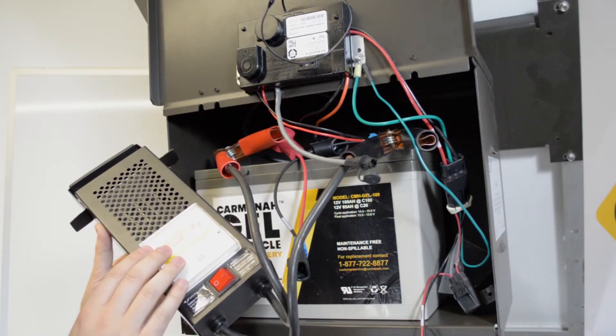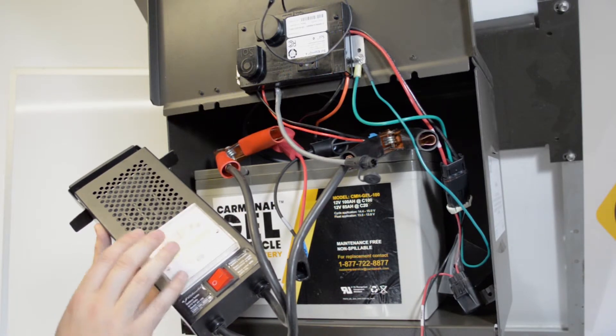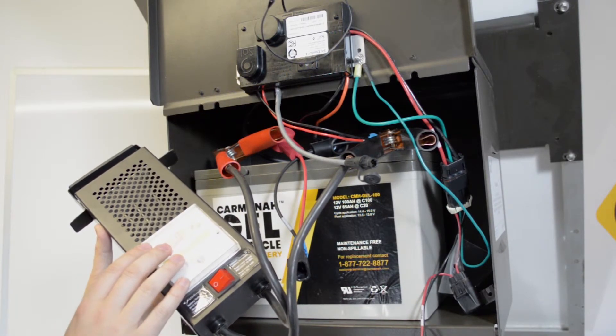While this load test is particularly more than what the fixture would draw from the batteries, it still gives a good indication of the battery health and if they need to be replaced.